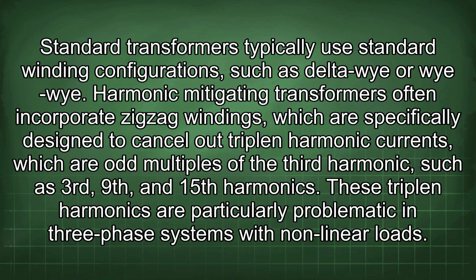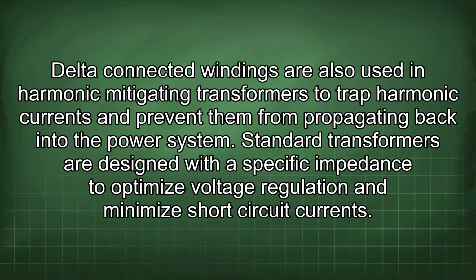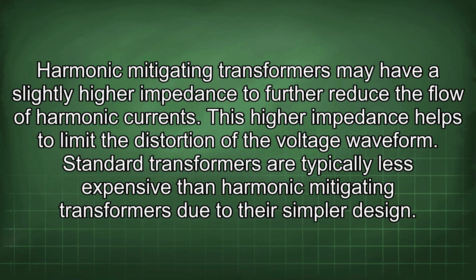These triplen harmonics are particularly problematic in three-phase systems with nonlinear loads. Delta-connected windings are also used in harmonic mitigating transformers to trap harmonic currents and prevent them from propagating back into the power system. Standard transformers are designed with a specific impedance to optimize voltage regulation and minimize short-circuit currents. Harmonic mitigating transformers may have a slightly higher impedance to further reduce the flow of harmonic currents.